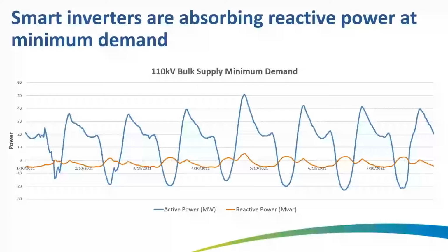Another thing that I'd like to sidetrack on a little bit here is how regularly we now see our reactive flows are capacitive. Historically, we've tended to assume that the reactive demand on our system is inductive, but during the middle of the night, we see consistently capacitive draw across all of our distribution networks now, and that only tends to disappear in the peaks, and also now in the middle of sunny days when all those inverters are providing reactive compensation.